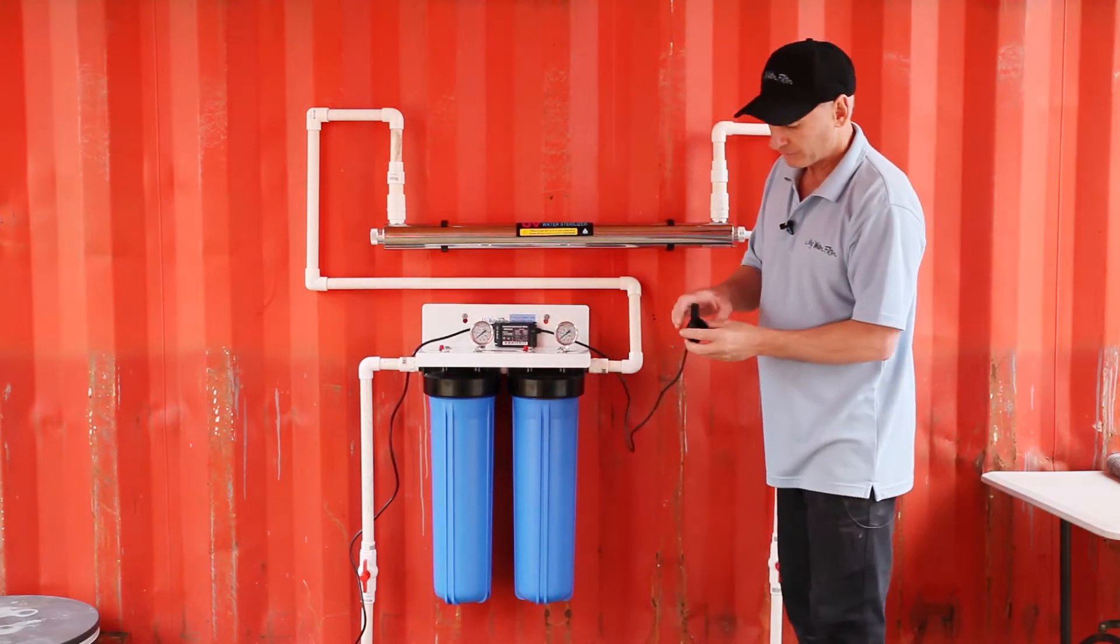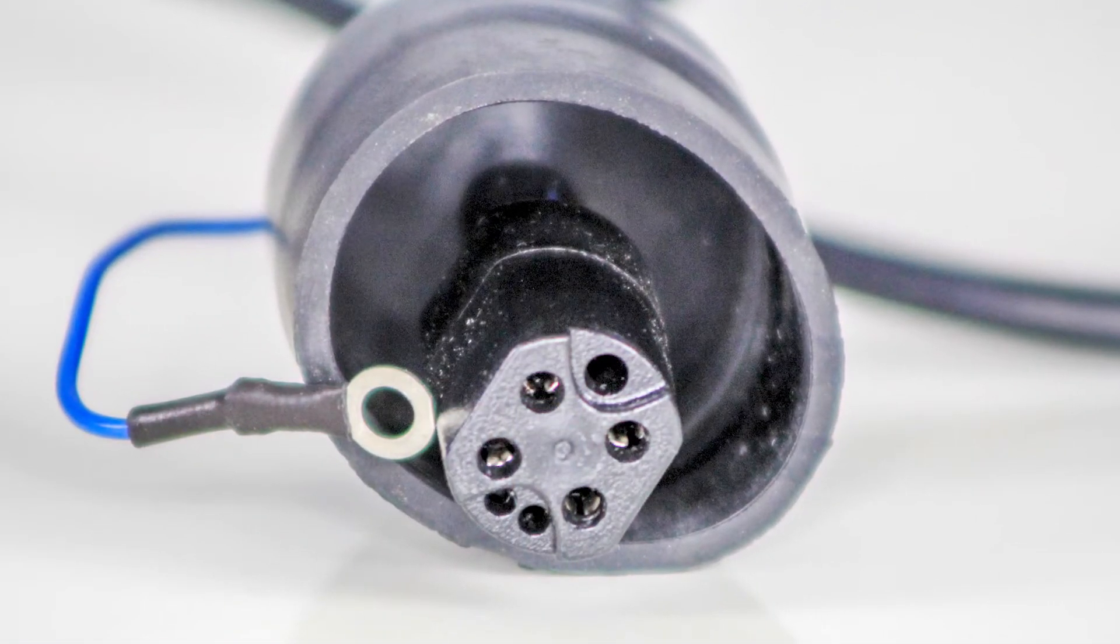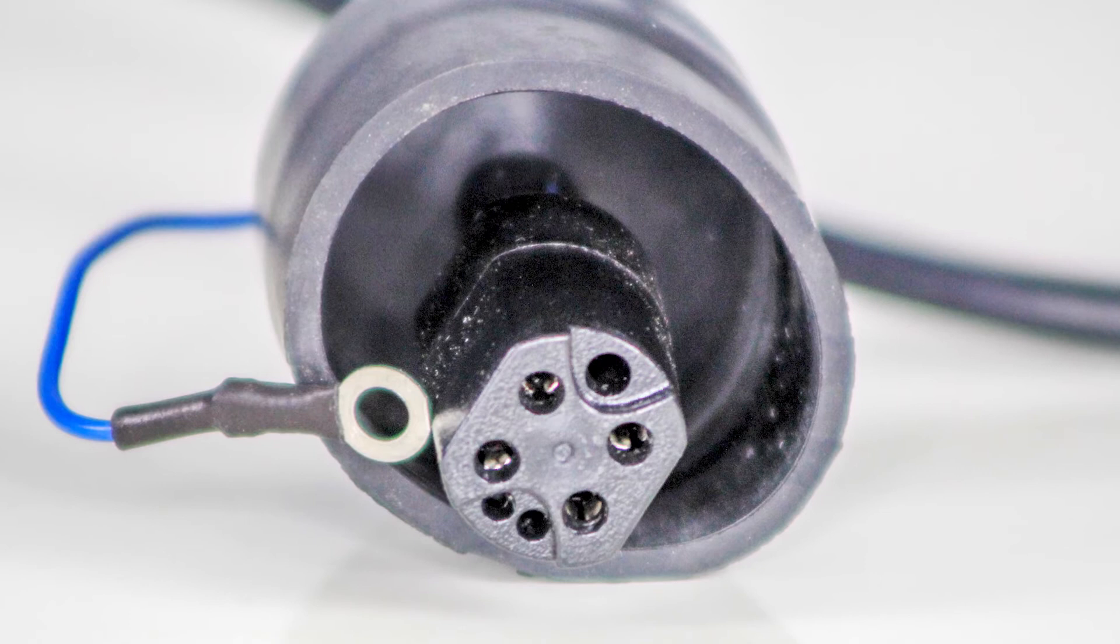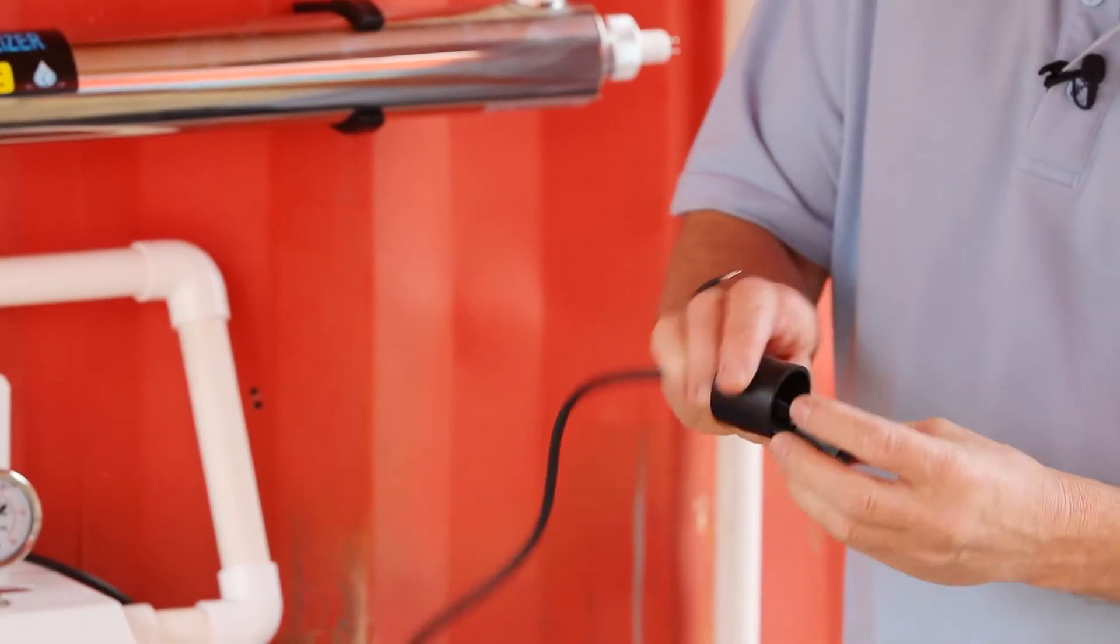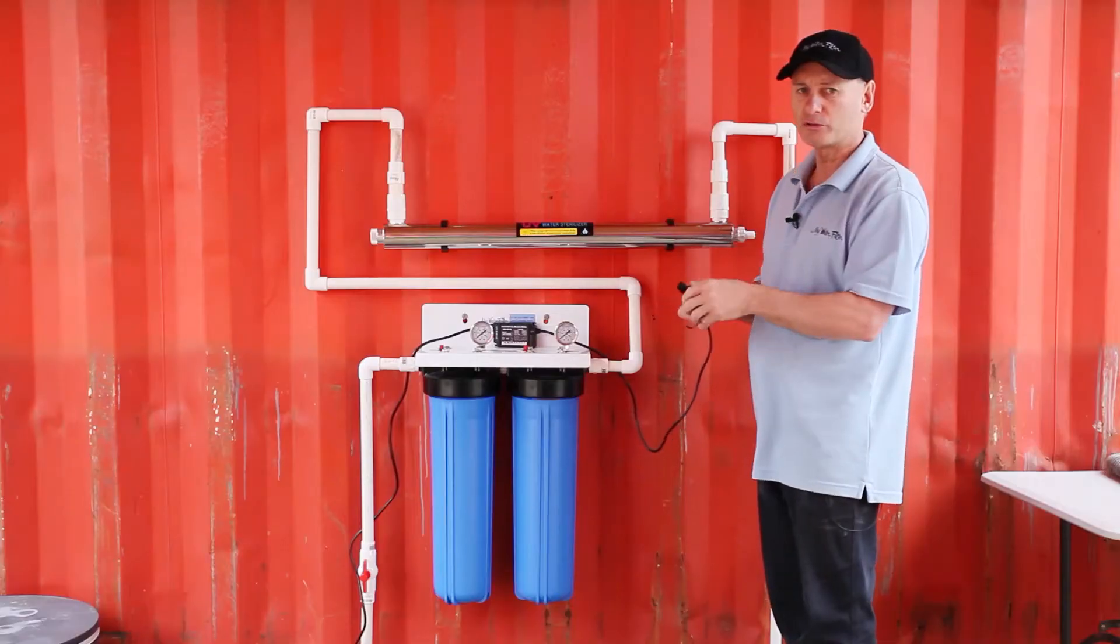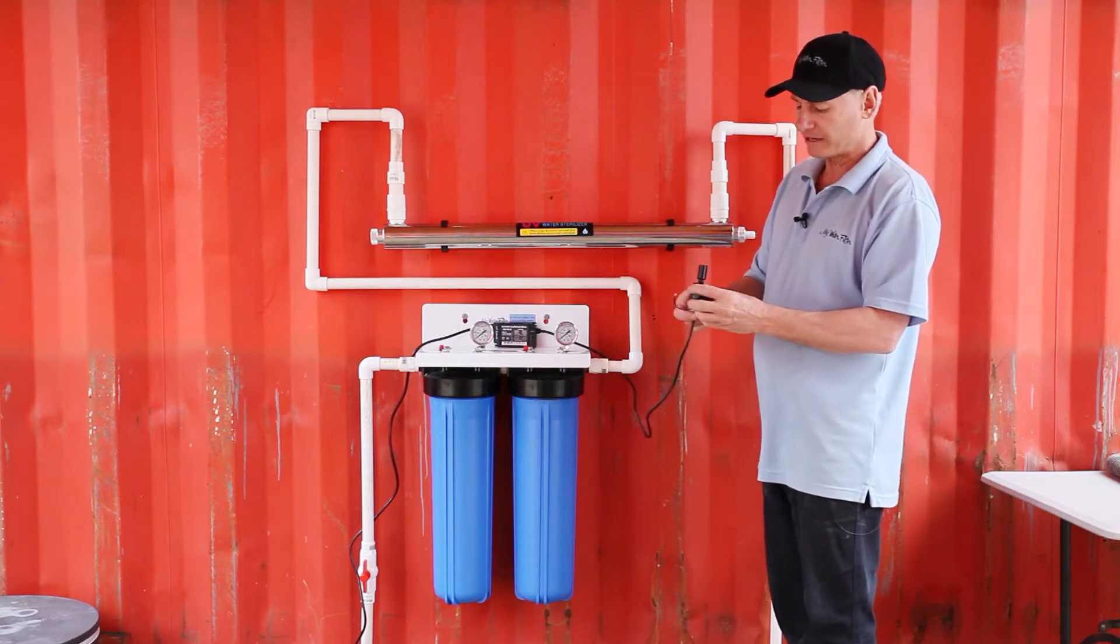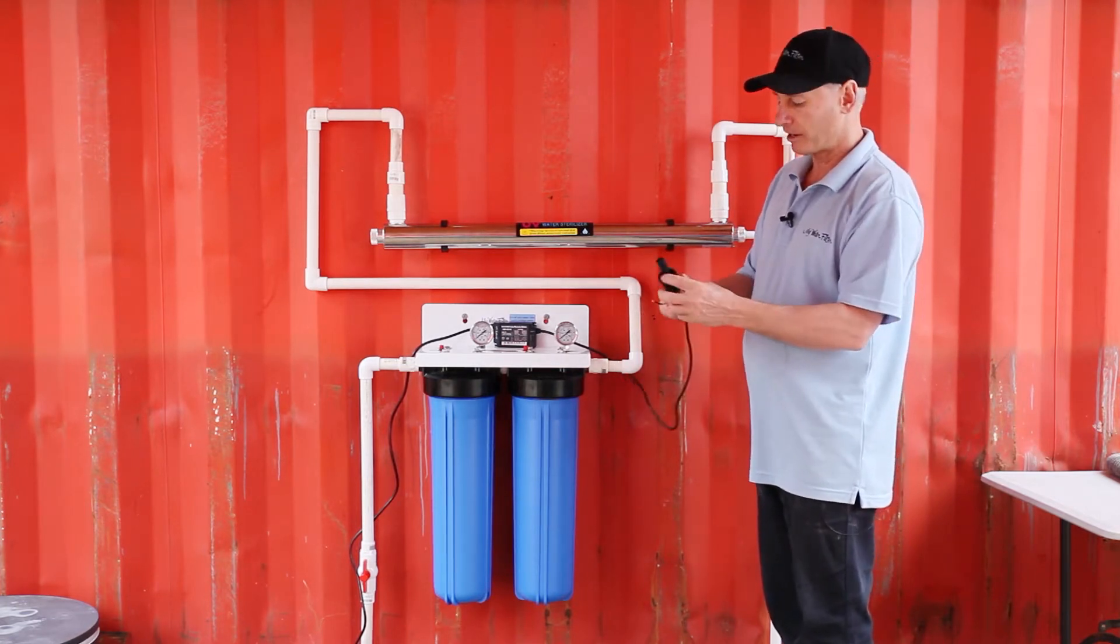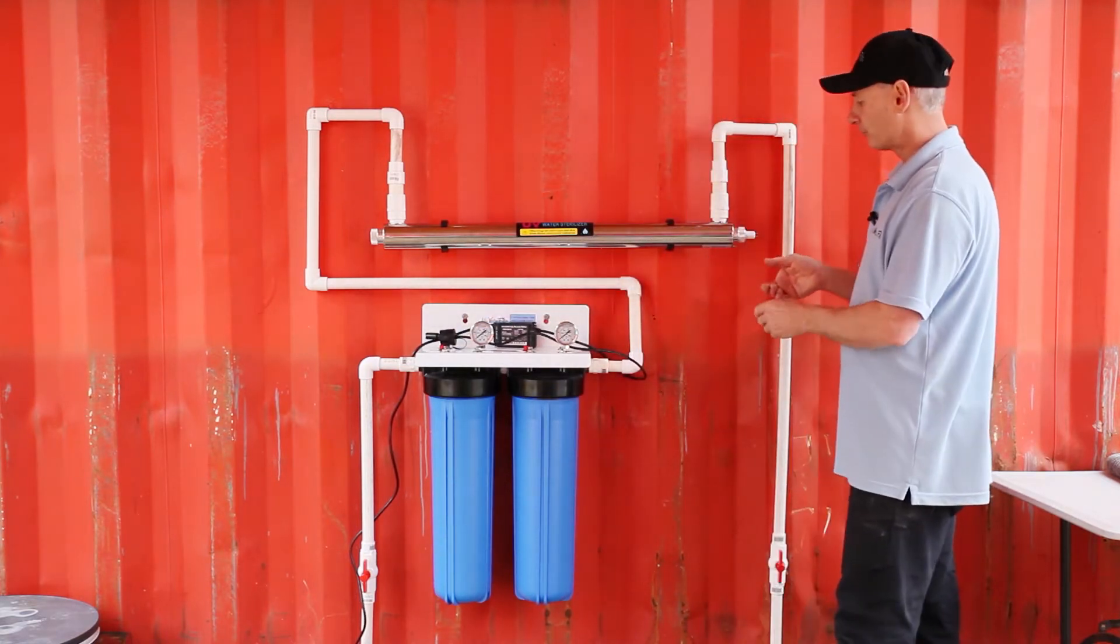With this part here, I'm looking inside. I'm going to get a cloth, give it a wipe out. Any cobwebs, spiders moved in, bugs, we want them out. Give it a blow, make sure it's nice and clean, no moisture in there. If there is, clean it up. We want this to go for the whole year. Get it back to as close to new condition as you can, and then let's try and keep it that way. This is still looking very good under the shelter.